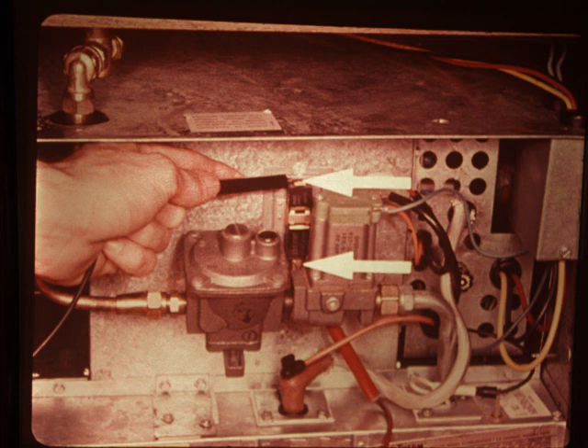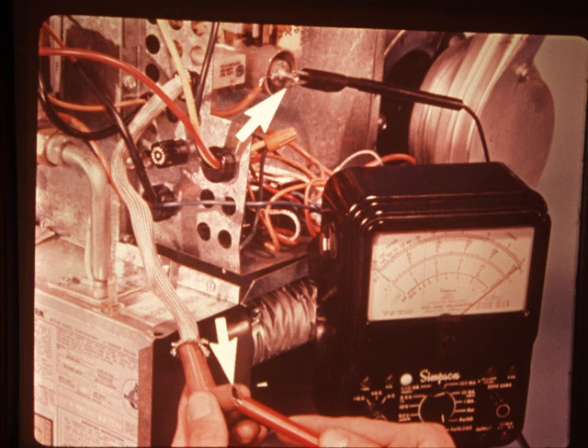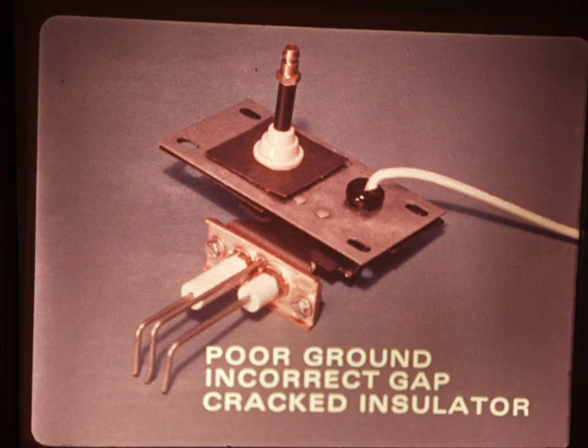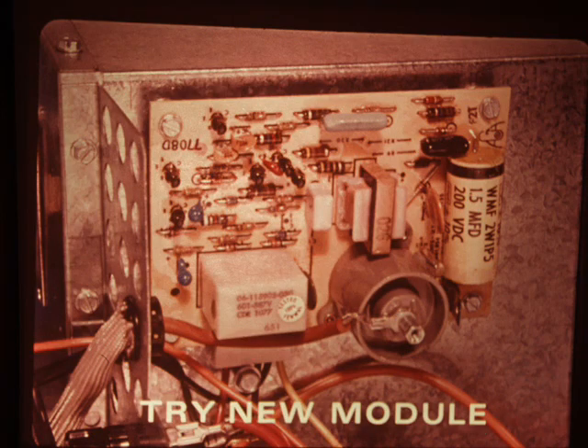Also, check continuity through the limit switch, which is in series with the sail switch. Check for an open or short in the high voltage lead to the igniter. If it's okay, examine the igniter itself. Look for a poor ground, an incorrect gap between the igniter electrodes, or a cracked ceramic insulator. The only remaining reason why you're not getting an ignition spark is a faulty control module. There's no way you can test it, so try operating the furnace with a new module installed. Don't discard the old one until you're sure it's defective.